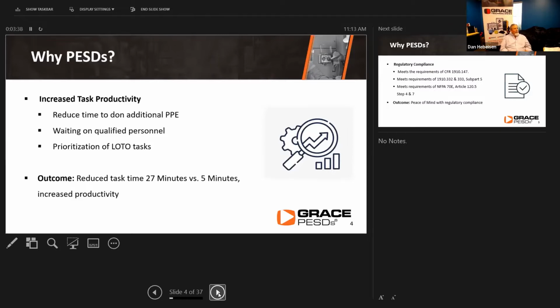Speaking of increased productivity, one of the things that can happen is that we're able to take a high incident energy task and reduce the amount of time that it takes to put on the PPE, and then also reduce the incident exposure. As we do that, it makes a pretty significant difference in the time it takes to do that task.